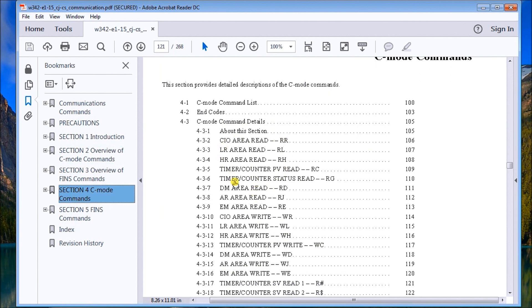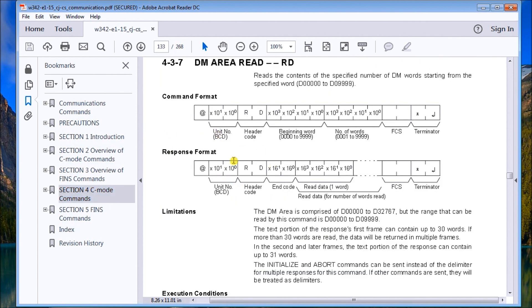We have the C mode commands — all the commands we can utilize are listed here. Looking at data memory read, we send: the at sign, unit number, header code RD, beginning word, number of words, checksum, and terminator. We receive back: the at sign, unit number, header code, end code, then each data memory word in sequence. We'll be reading 10 data memory registers, followed by the checksum and terminator.